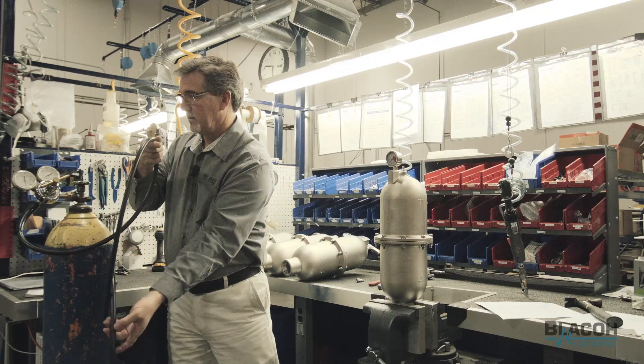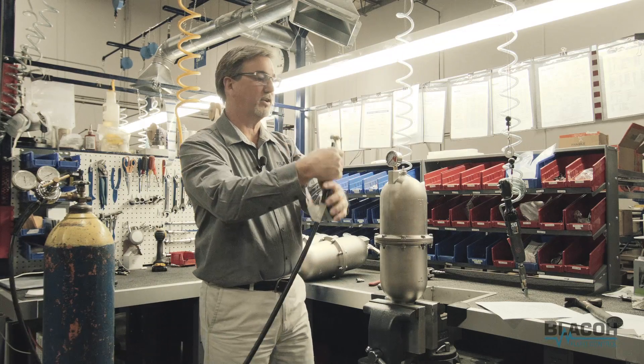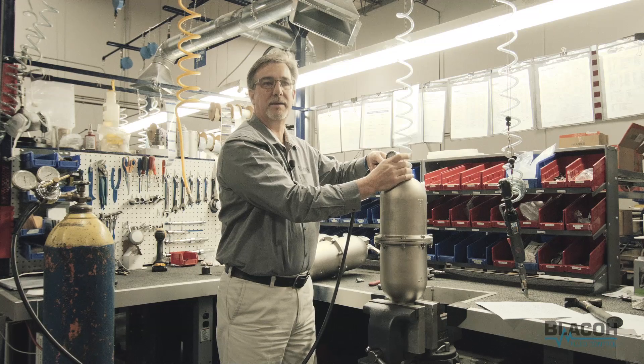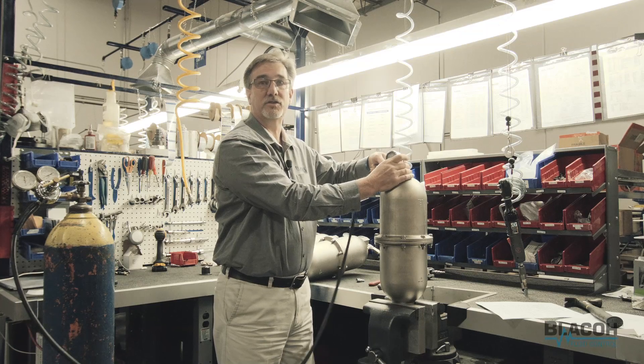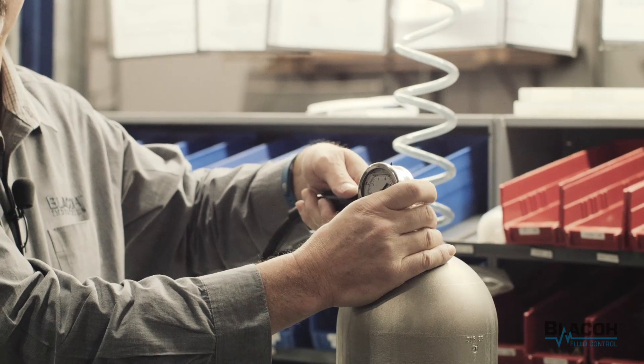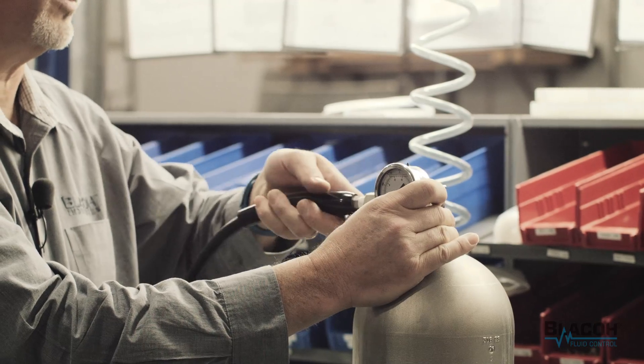These are used for pressurizing the unit to pressures greater than 150 psi. Keep in mind the rated pressure of the pulsation dampener so that you don't exceed it, especially with these nitrogen tanks because they have pressures of greater than around 3,000 psi. Make sure that you don't go greater than the rated pressure of your unit.